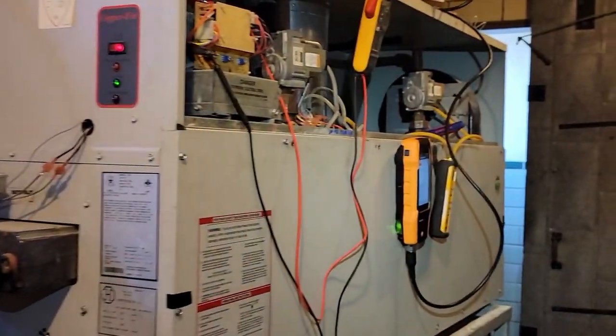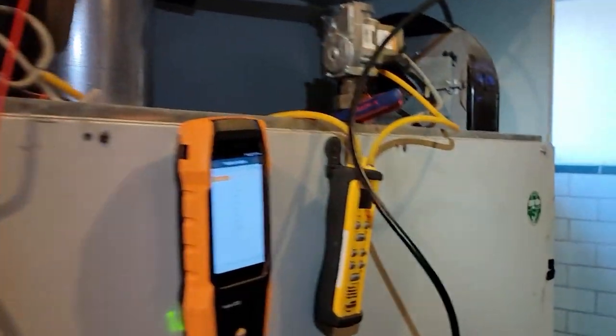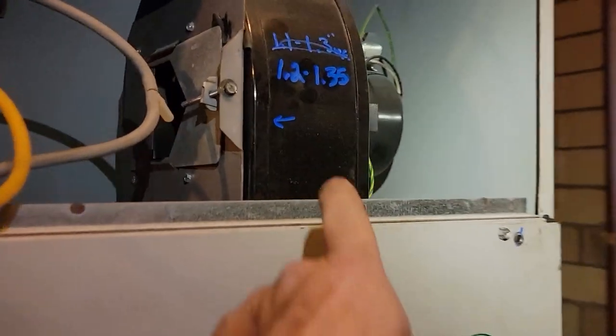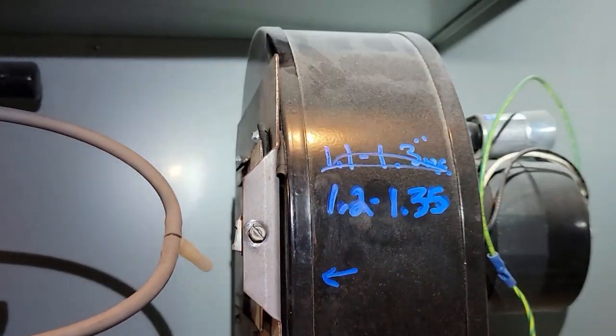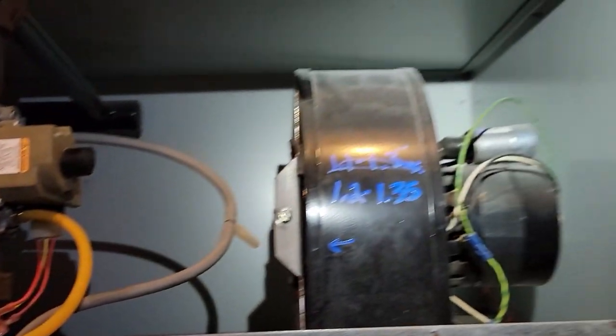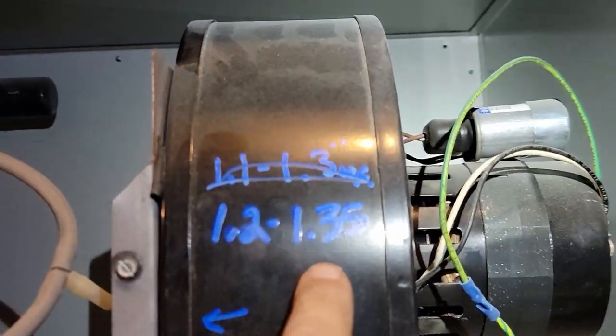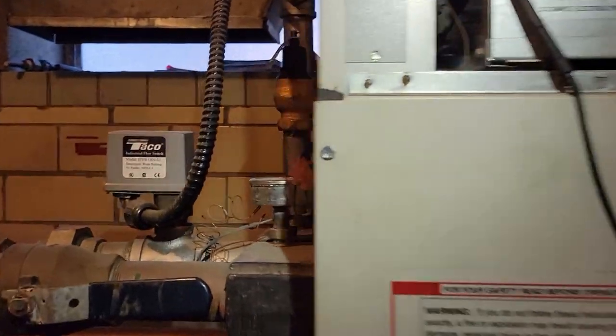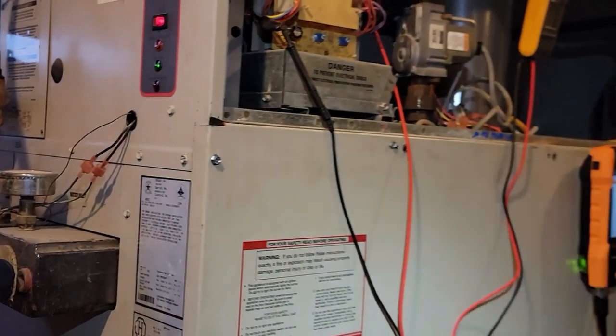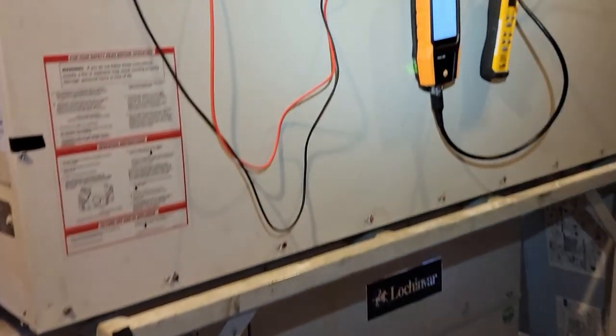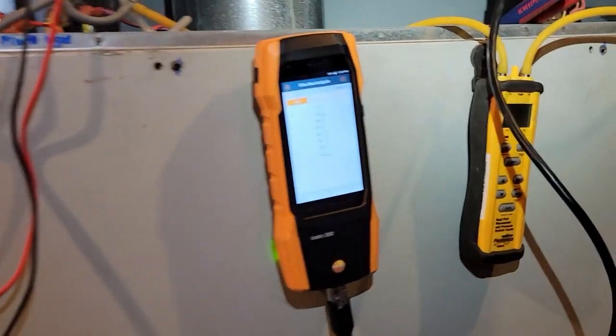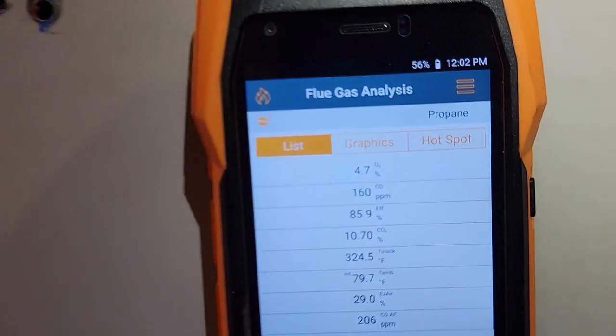To me it seems like it should stay running. I bet you anything. I mean all I did was I brought the gas pressure back up a half a turn and I tweaked this down to maybe 0.2 less than what it was. I had it at 0.13, which was below what they said the max was. This is a 2004 boiler, but it's in good shape yet. It's in a church and it's not like it's getting used a lot. We're running 160s.